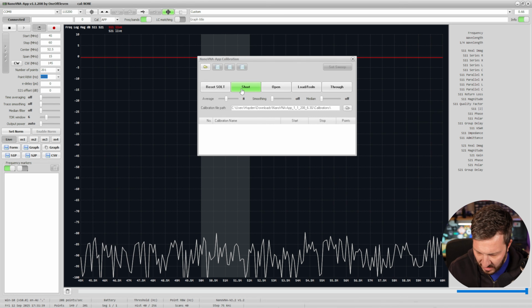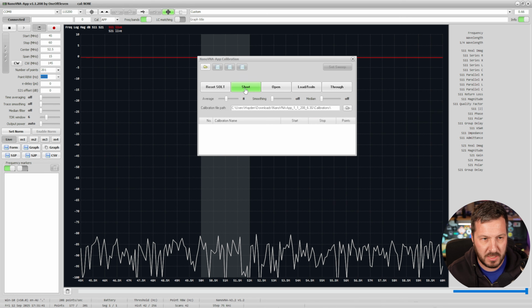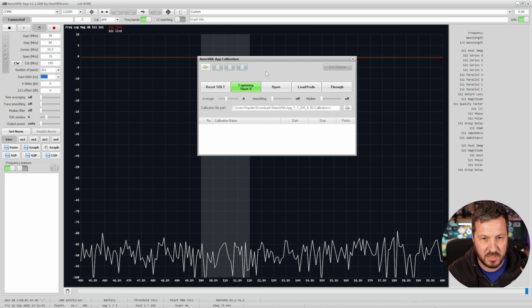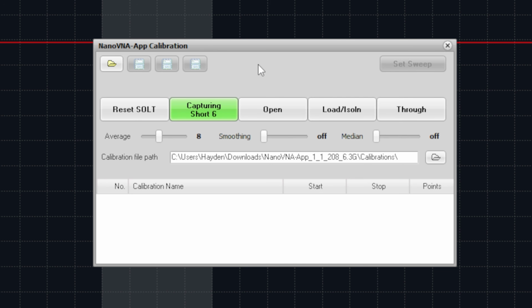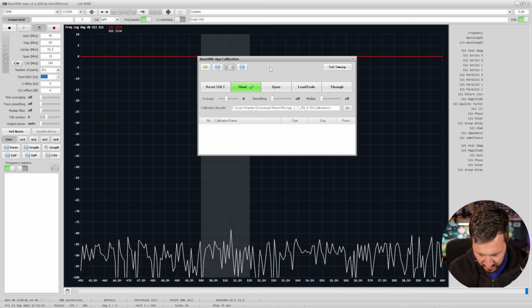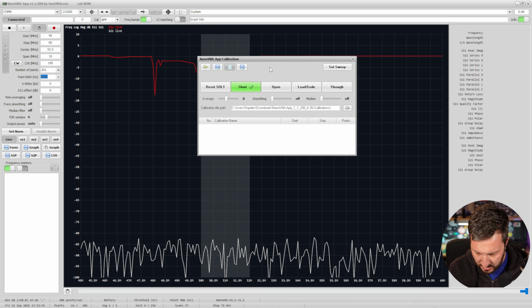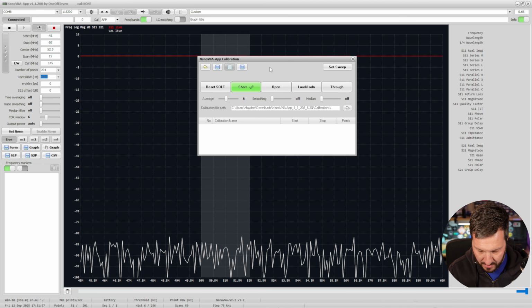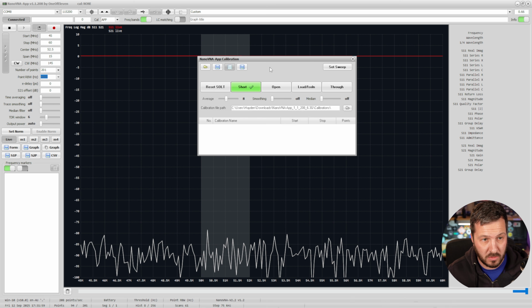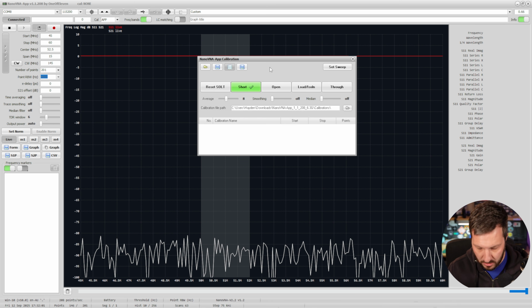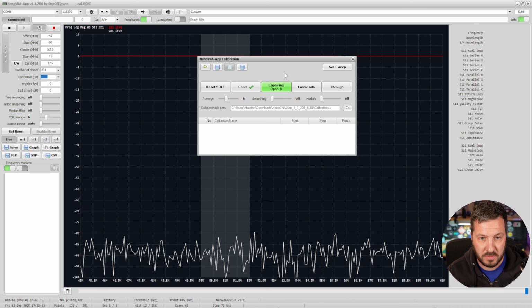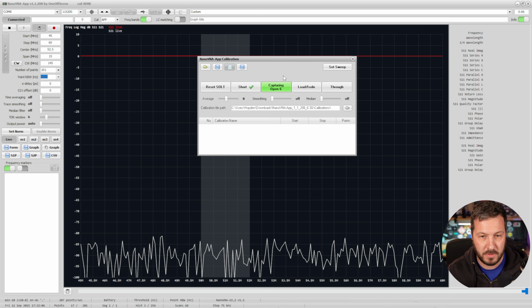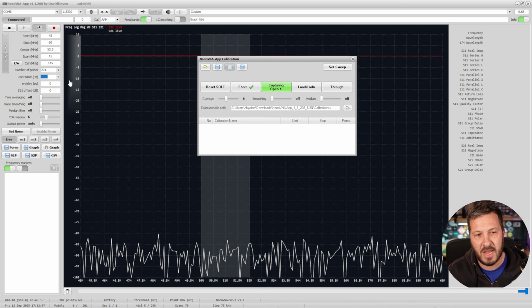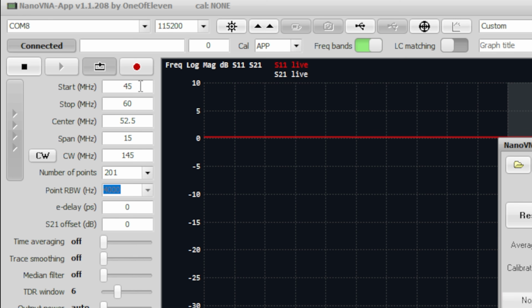Now, as I go through this calibration, how long it takes depends on how many points you've got. It should give you a countdown here as it captures the short connection. Once we've done these calibrations, they apply to the frequency range we're actually scanning over. So I've just put on the open, so we hit open and we'll capture the open. What I mean is that we're calibrating this for our sweep here of 45 to 60 megahertz.